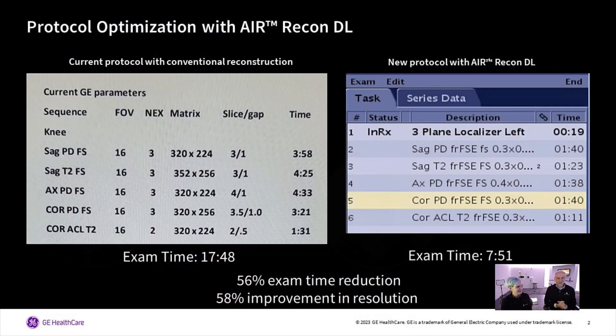Let's jump over to the console and check it out. So we are here at the scan console. Before we jump into that, we wanted to share with you some results of a recent scan that was done. We took a capture of their current protocol — that's the capture on the left. The exam time there is about 17 minutes just using conventional reconstructions. The capture on the right is the modified version of the same protocol, and it's significantly reduced in terms of exam time — down to about seven minutes.